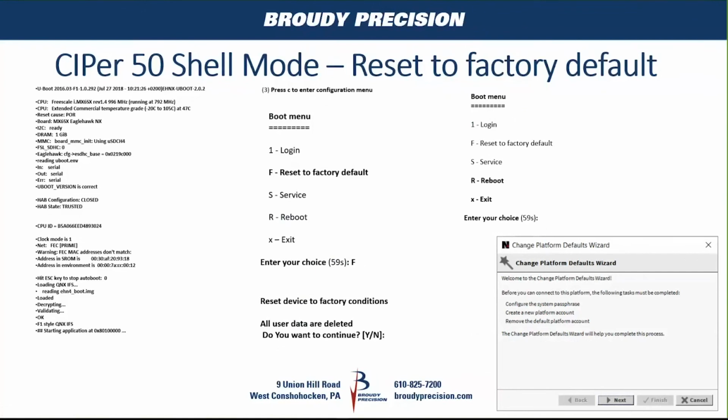It also blows away the station that you have in there, and the modules or whatever you used when you configured or commissioned your controller. But it keeps it at the current firmware version that you were working in. So if it was sitting at 4.8, you're still going to be at 4.8. So this is a way to go back to defaults and back to a new image, I guess, at the version that you were running.